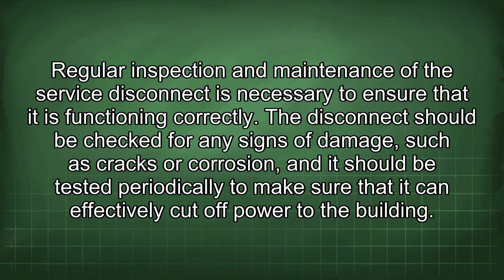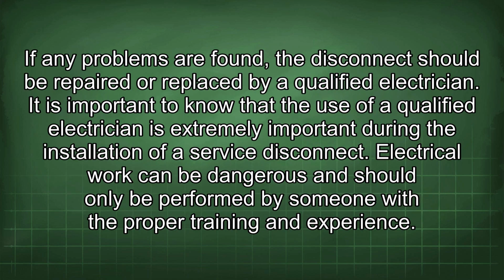Regular inspection and maintenance of the service disconnect is necessary to ensure that it is functioning correctly. The disconnect should be checked for any signs of damage, such as cracks or corrosion, and it should be tested periodically to make sure that it can effectively cut off power to the building. If any problems are found, the disconnect should be repaired or replaced by a qualified electrician.